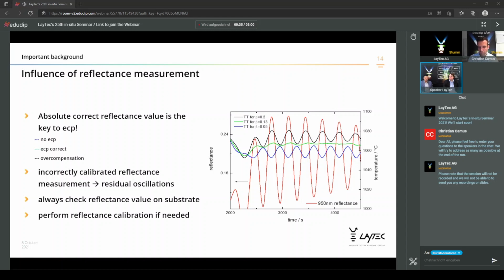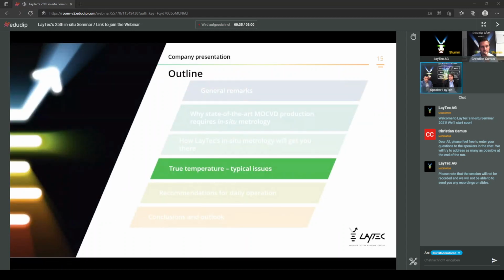So we recommend that you always check the reflectance value on the substrate. For example, for sapphire, the reflectance value you read will be 7.5%. If you read other values, you need to perform the reflectance calibration. Well, now Heiko will report typical issues we received from the field, or what we see in many cases in the field, what might happen.